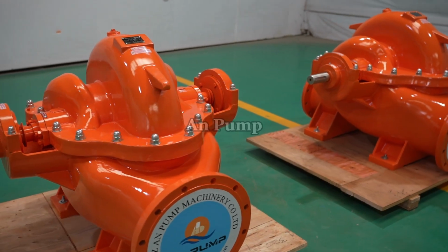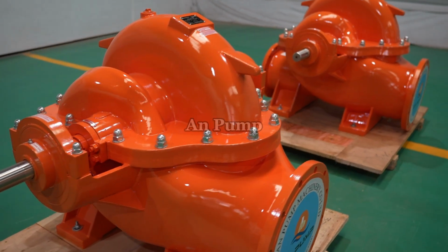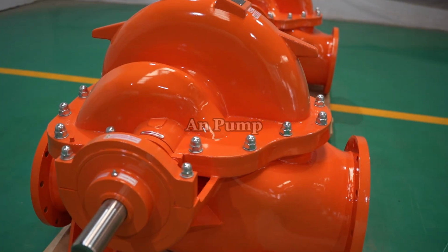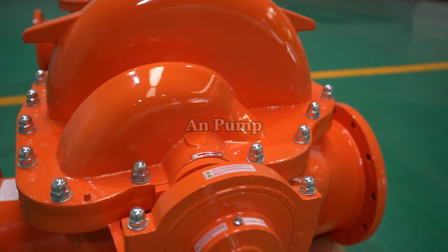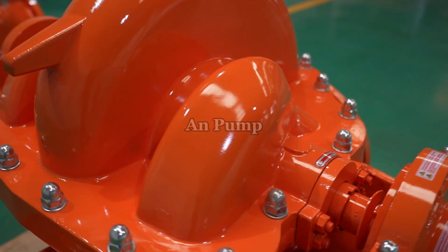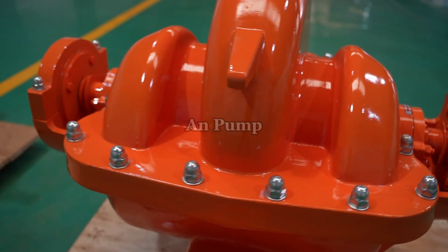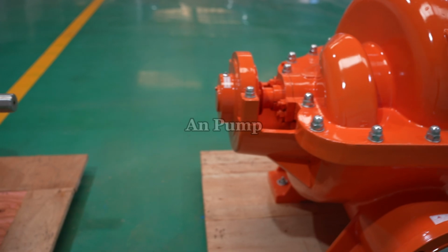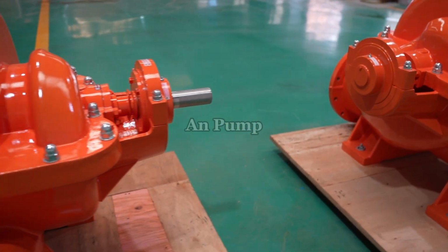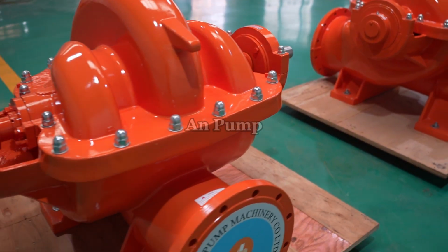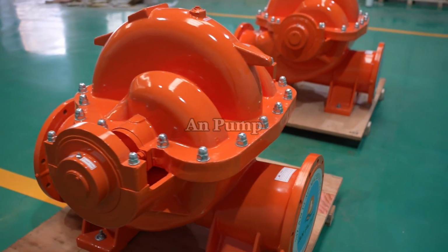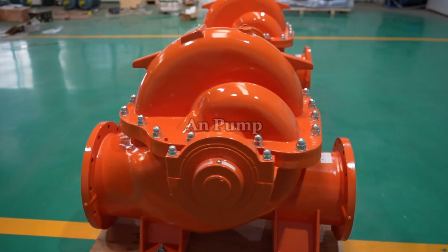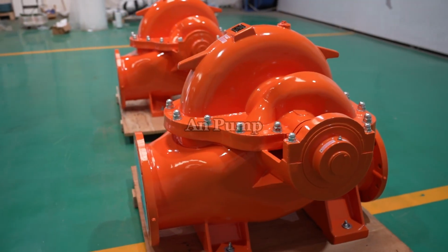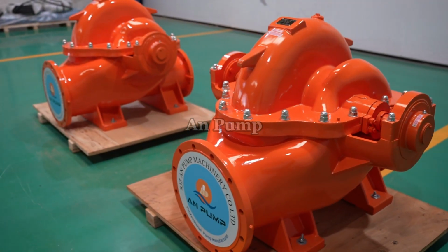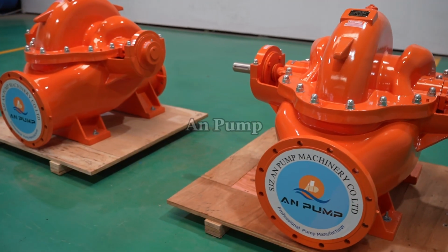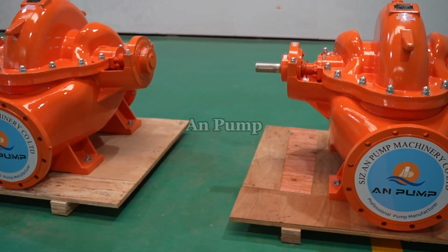Now let's move to type number 2, the split case pump. This pump is also called a double suction pump in many cases. The casing splits horizontally along the shaft centerline. You can unbolt the top half and lift it away, exposing the impeller, wear rings, and bearings without touching the pipes. The key feature here is the double suction impeller. Liquid enters from both sides of the impeller at the same time. That balances the axial thrust on the shaft, which is a big mechanical advantage at high flow rates. Less thrust means longer bearing life and lower maintenance costs.